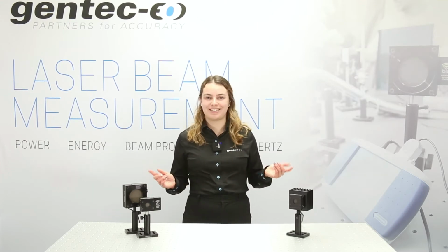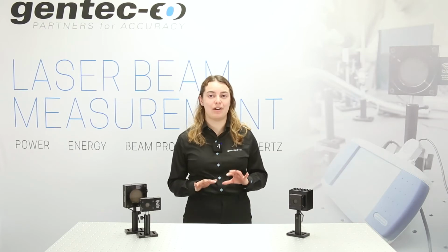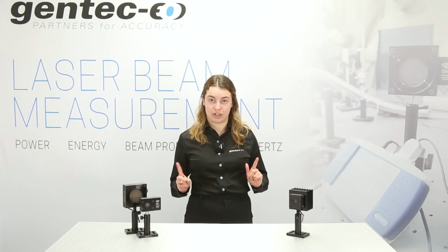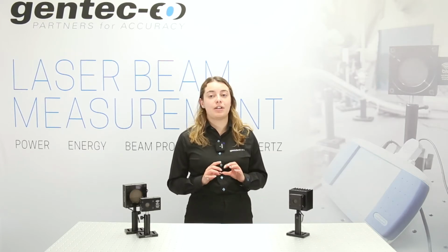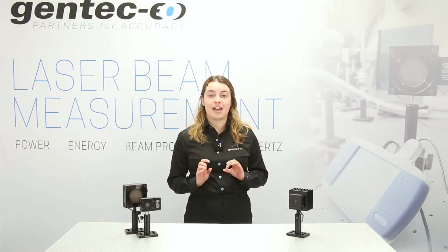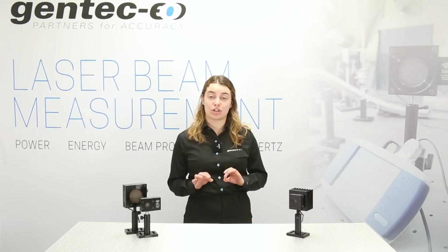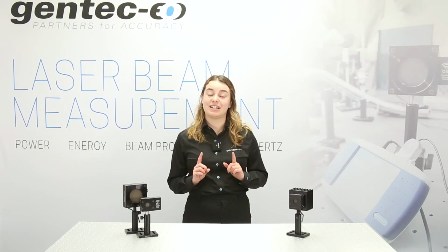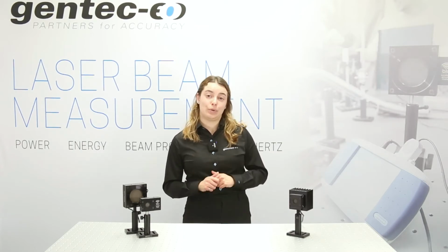Of course, this doesn't take into account the minimal beam size required to avoid exceeding the power density damage threshold of your detector. It is possible that your beam needs to cover more than 10% to avoid marking the absorber. If you are not sure about damage threshold, check on your product's datasheet or in the user manual.